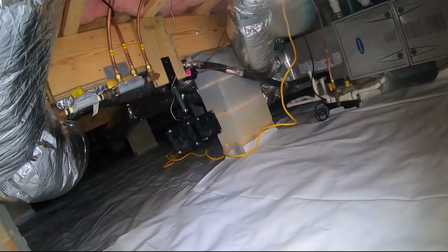This system is the latest upgrade to the system, and it's called the ACE controller. The ACE controller has the latest software available for the Atmox program. So we're very happy to be deploying that system. And something else that's also new with this upgrade is we can set the dead corner fans at their own relative humidity level. So if the dehumidifier is off and the exterior fans are off, I can still run the dead corner fans to operate independently, to always be stirring the air in this environment.